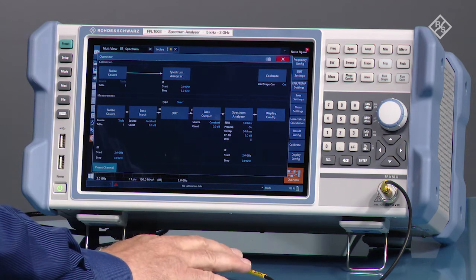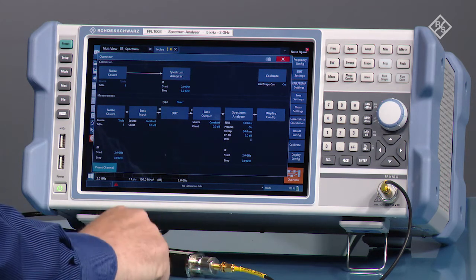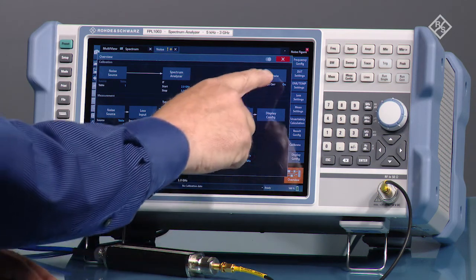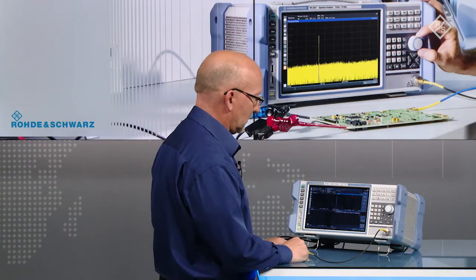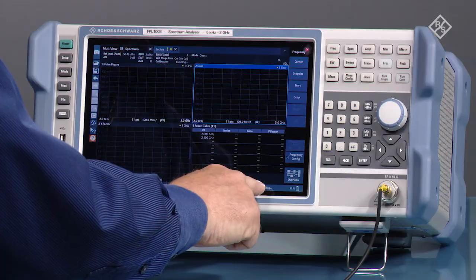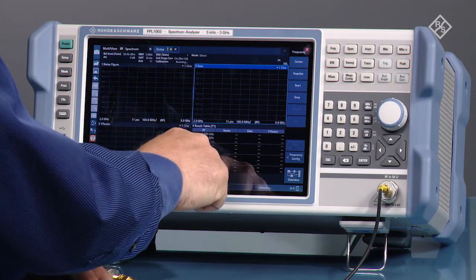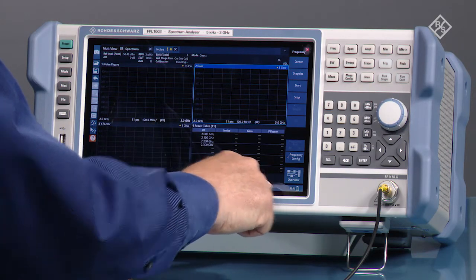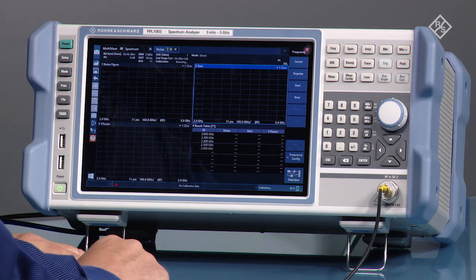We have connected a 28 volt noise source right here to the spectrum analyzer so all we're going to do now is calibrate. We can see now the calibration has started and we can see the progress right here. It will switch to ready when we are done.